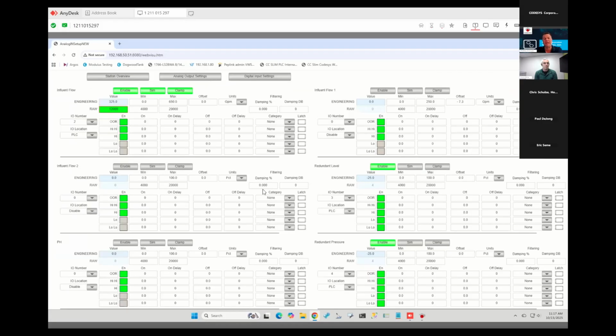I also have all of my analog settings here. So for influent flow, effluent flow, whatever they might do, pH, most of the systems now are doing redundant pressure transducers and redundant level transducers. So those are coming in live to the system. So the customer operator knows, hey, I've got a discrepancy between my primary, my redundant, and I can change scaling. The nice thing here too is not only am I selecting where that I/O is mapped, this comes back to if we have one that burns up, we have one that goes bad, I'm able to now very quickly and very efficiently change where it's mapped. There's nothing to do with the program. All we're doing here is mapping hardware.